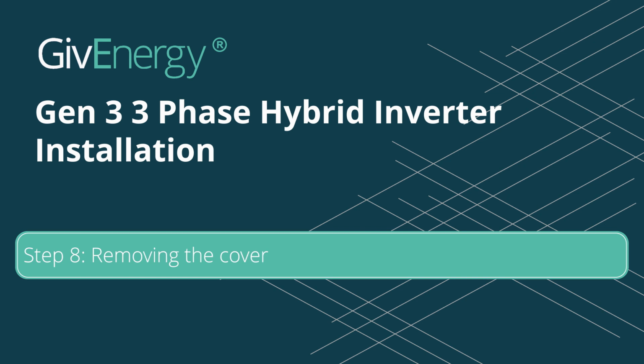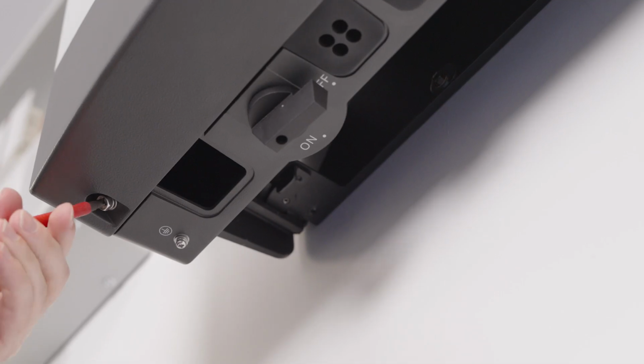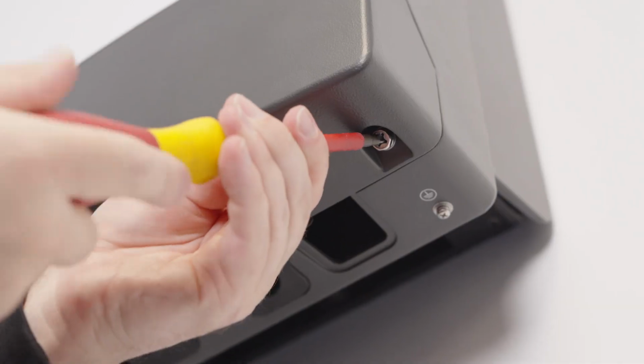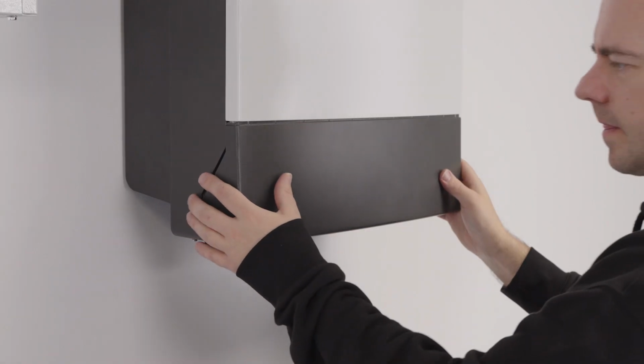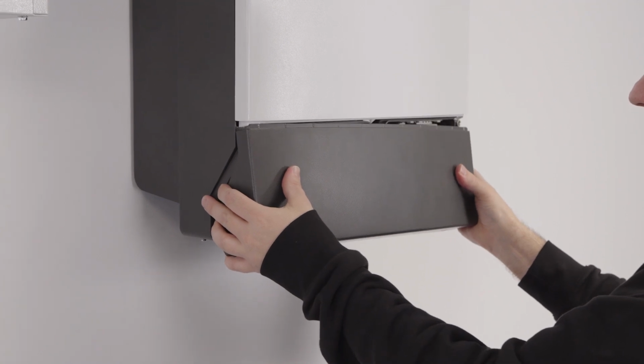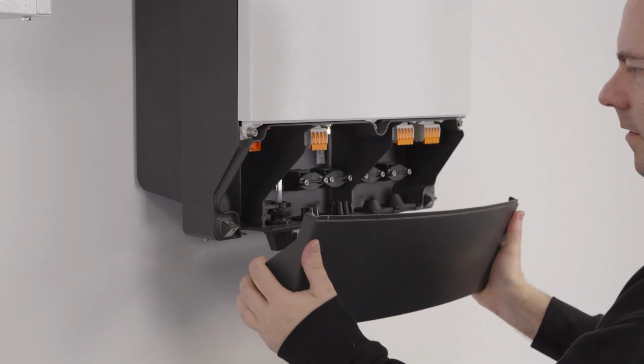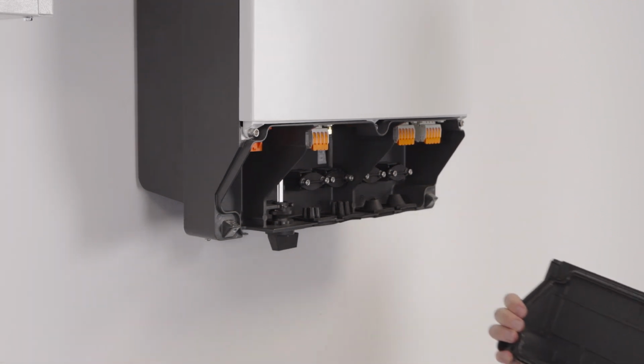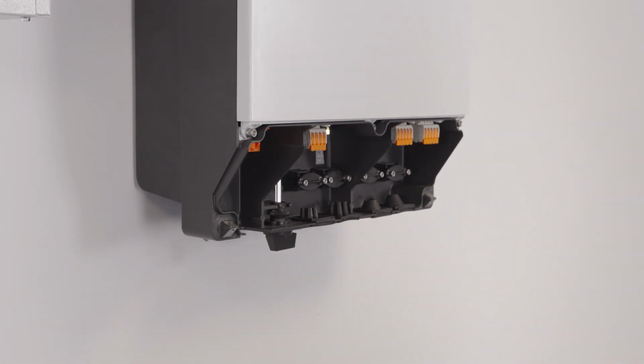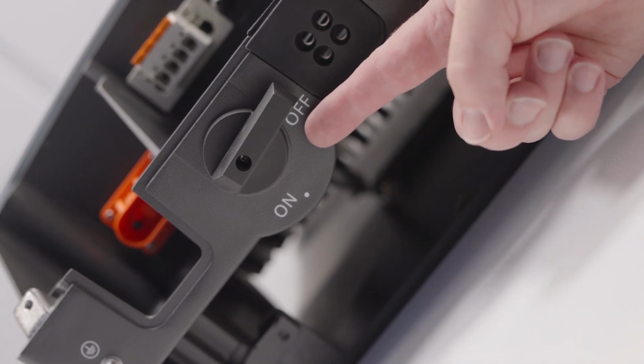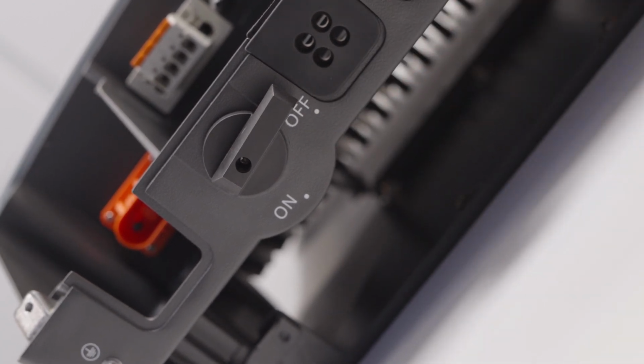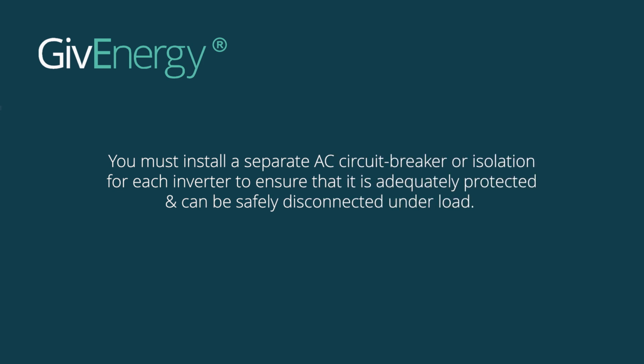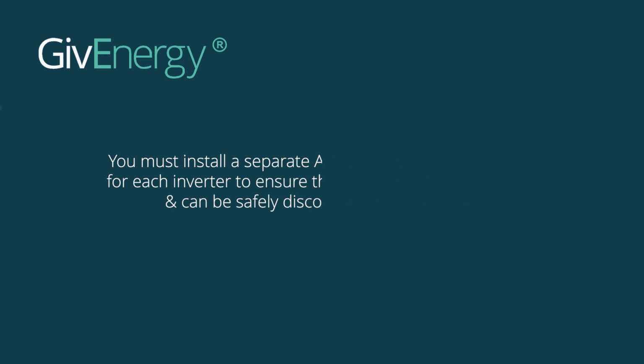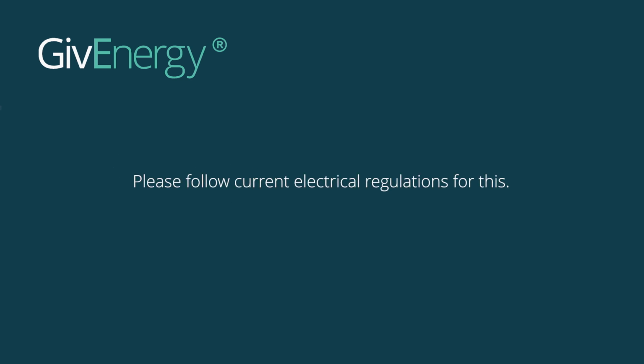Step 8. Removing the front cover. Remove the two fixings on the bottom of the inverter with the appropriate tool. Carefully pull the bottom cover slightly outwards, then straight down to remove it. Don't pull the cover outwards or towards yourself fully, as this can damage the cover, preventing it from being replaced securely. Make sure the DC PV isolator is switched off on the GivEnergy inverter. You must install a separate AC circuit breaker or isolation for each inverter to ensure that it is adequately protected and can be safely disconnected under load. Please follow current electrical regulations for this.